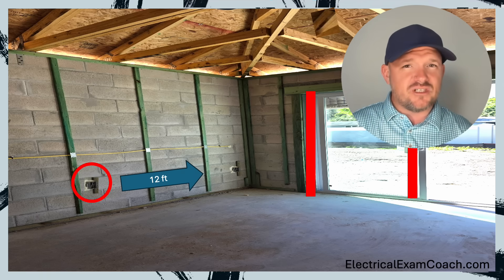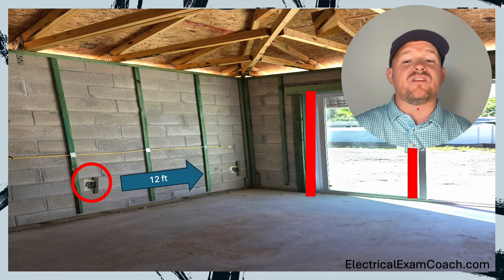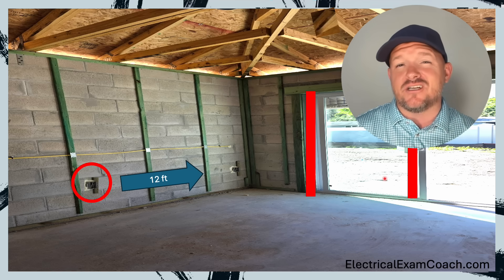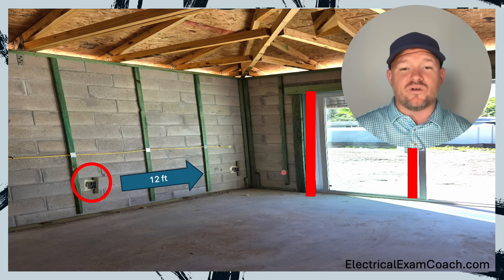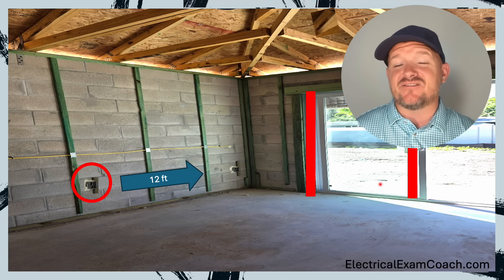The question for today is: where does this wall space end? Does it end right here where this fixed glass panel starts? Or does it end right here where this fixed glass panel ends? Because it's going to make the difference of whether or not this installation is code compliant. If the wall ends here, it looks like this one's within six feet — we're fine. But if the wall space ends here, that does not look like it's within six feet.